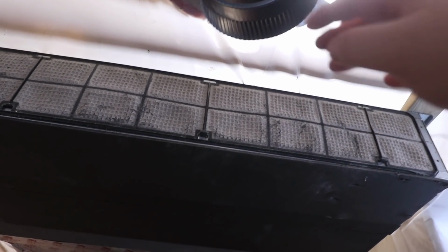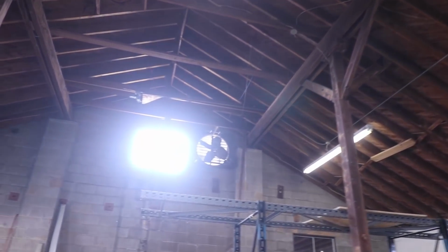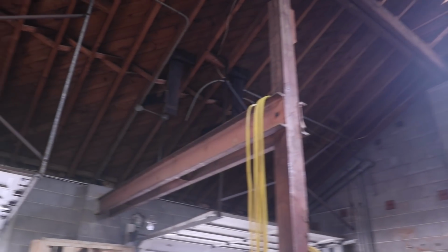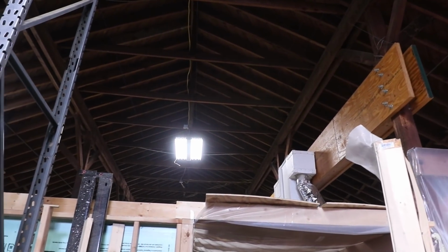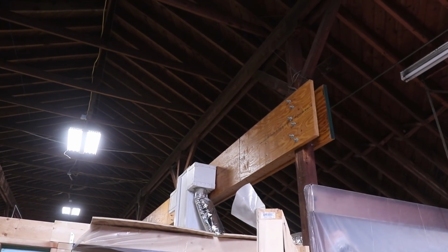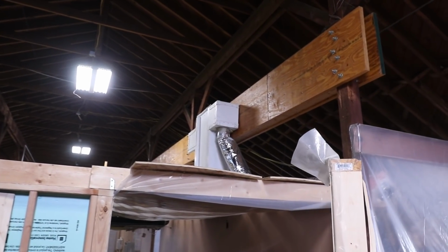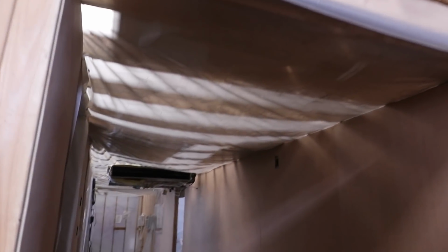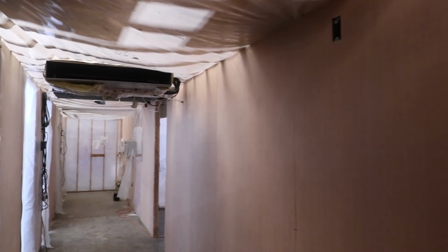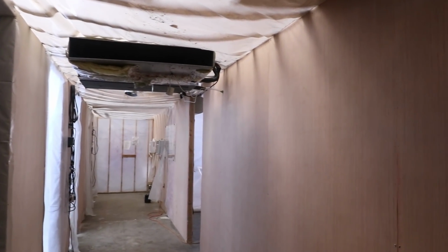The HRV system pulls air out of incubation, dumps it out in the warehouse, but manages to run fresh air through a radiator, fins, to recapture energy so that if we're cooling incubation, we get to recapture some of that cool air and then dump it into our preconditioning room. So that's now fresh and cool, and we actively cooled only one room, but now we're getting to reuse that colder air, meaning we get to use it twice.